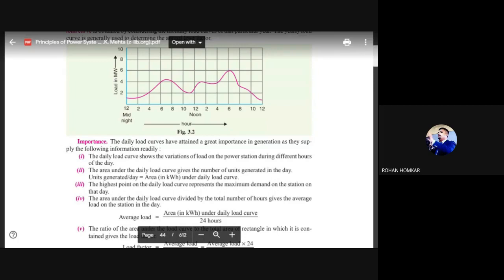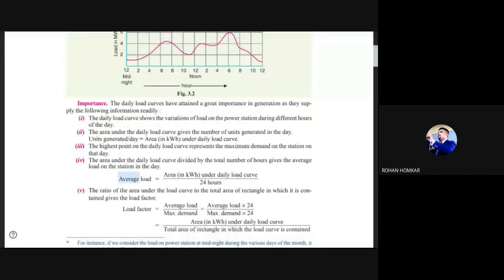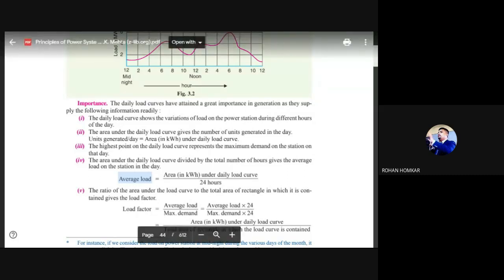The highest point on the daily load curve represents the maximum demand on the station on that day. If a power station has a maximum demand of 10 megawatts, we need to arrange plants with capacity to generate 10 megawatts under maximum demand conditions. The area under the daily load curve divided by the total number of hours gives the average load on the station. Average load is the load present on the power station in a given period — day, month, or year.